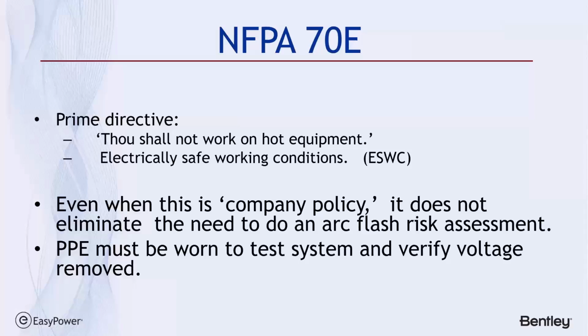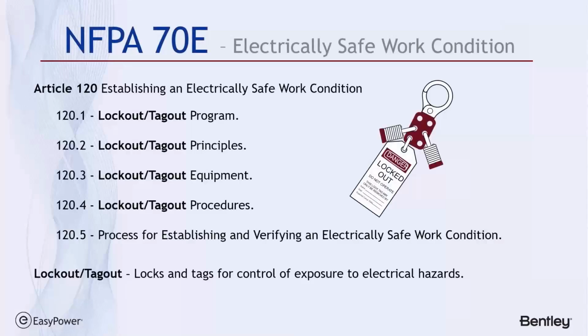The steps involved in establishing an electrically safe work condition are to de-energize the equipment, test the equipment, actually test it to make sure it's hot or not hot for starters, open the system connection, the breaker supplying the energy, and test it again to make sure it's de-energized. During that process you must have on the proper PPE. So this requirement doesn't negate the need to do an arc flash study.